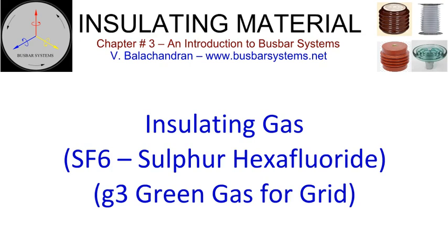Environmental concerns have led to the usage of the gas mix 80% nitrogen plus 20% SF6 and development of green gas for grid, G3. Gas-insulated bus, with these insulating media, are in commercial operation.